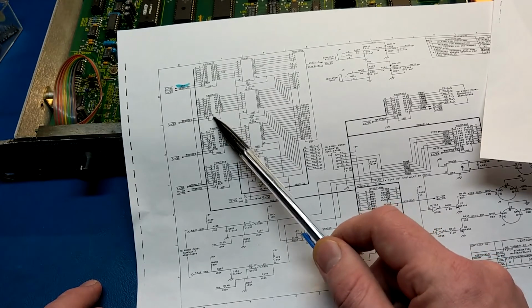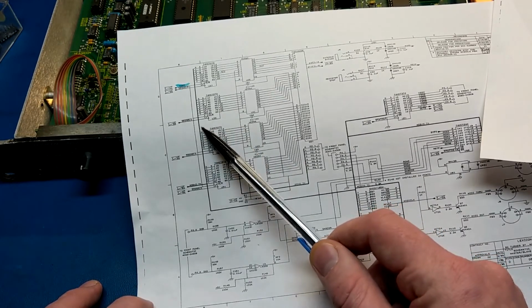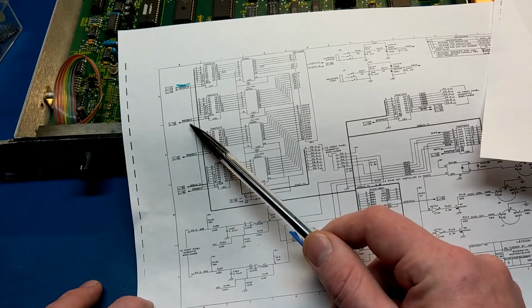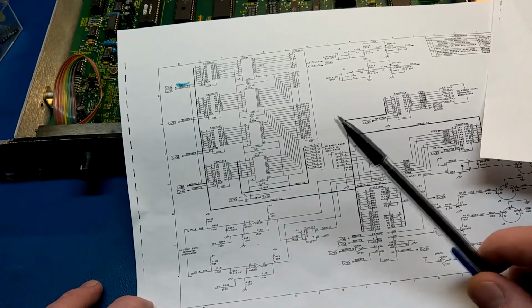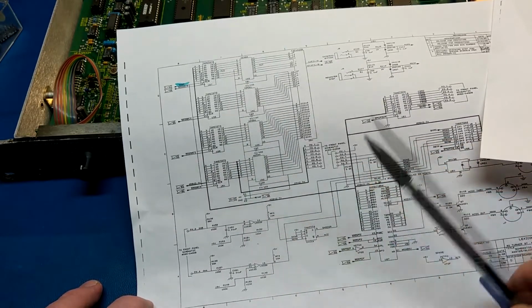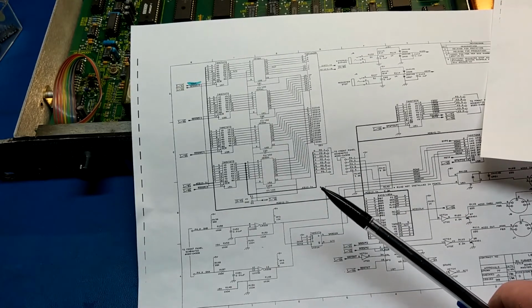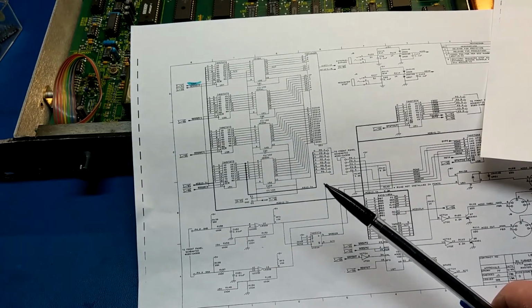And sure enough, after pulling this chip, the data bus is now operating correctly, the select pins are operating correctly, and everything else seems happy. So this chip had failed, and that was what the issue was with the digital section of this device.